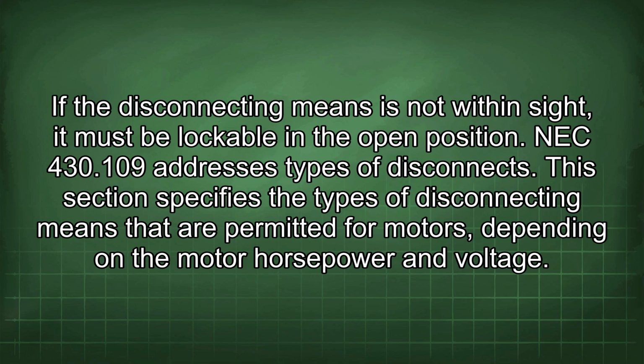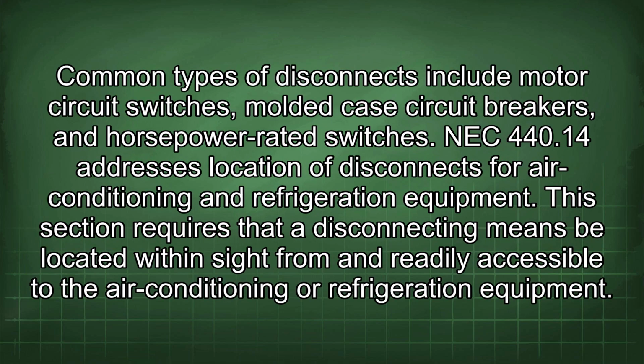This section specifies the types of disconnecting means that are permitted for motors depending on the motor horsepower and voltage. Common types of disconnects include motor circuit switches, molded case circuit breakers, and horsepower-rated switches. NEC 440.14 addresses location of disconnects for air conditioning and refrigeration equipment.